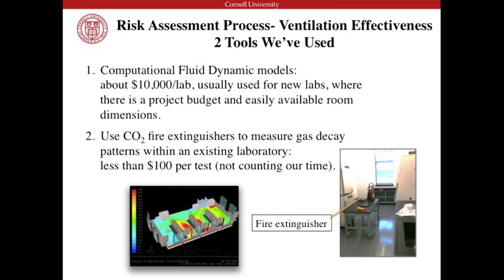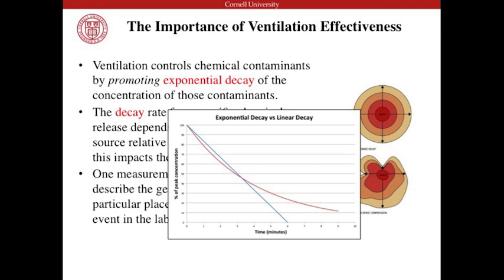Something important to keep in mind is that as the ventilation removes the contaminants, this is actually fluid dynamics. So we have points where the air comes in, and we have the exhaust points, and we're looking for how well that's being pushed and pulled through the space. When you have things like equipment, chairs, other furniture, the benches, there tends to be pockets. If the lab wasn't designed with effectiveness in mind, you could actually have the benches positioned in the wrong way so that it blocks the ventilation from sweeping.